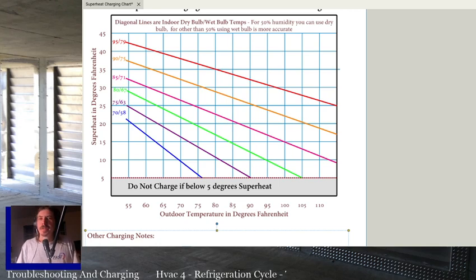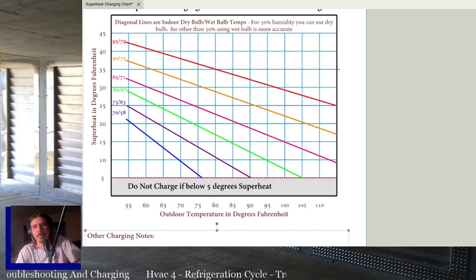So if we're talking residential splits, I don't know what you work on a lot. We're talking residential split systems, right? Generally wherever you're going to be hooking up your gauges is where you're going to end up measuring subcooling and superheat, unless you've got a weird situation. But you should always measure subcooling at the outlet of the condenser, because that's going to be the most accurate spot, and superheat at the outlet of the evaporator, because that's going to be the most accurate spot. But as long as you're within the line set, you're fine.